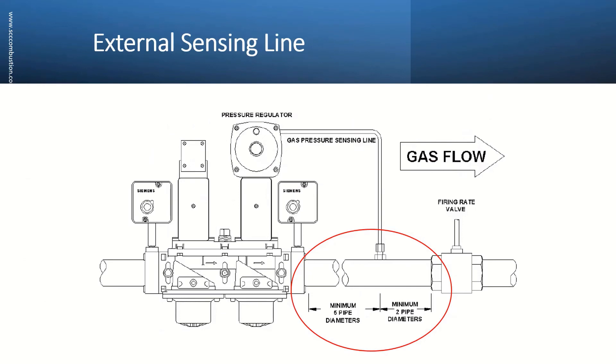The SKP25 requires an external gas pressure sensing line into the pipe downstream of the shutoff valve. We recommend 5 pipe diameters of straight run upstream of the sensing point and 2 diameters straight run downstream for a clean pressure sensing. We also recommend keeping the velocity downstream of the shutoff valve less than 120 feet per second. Usually the pipe size downstream of the shutoff valve is increased.